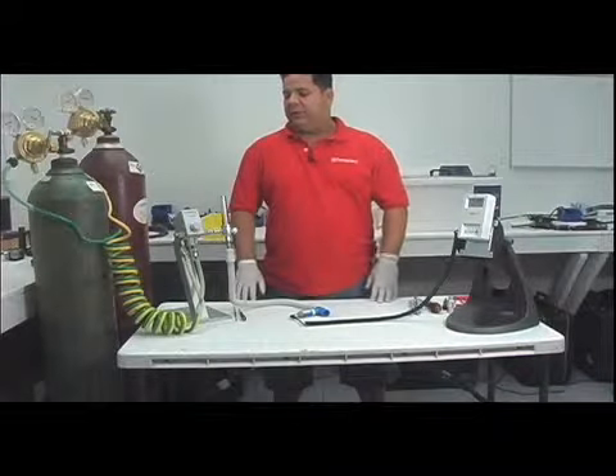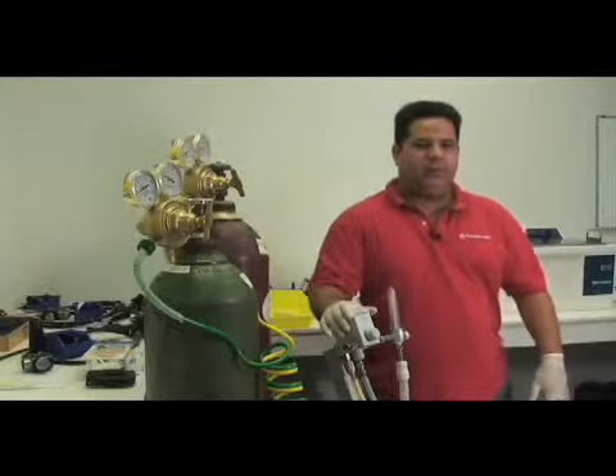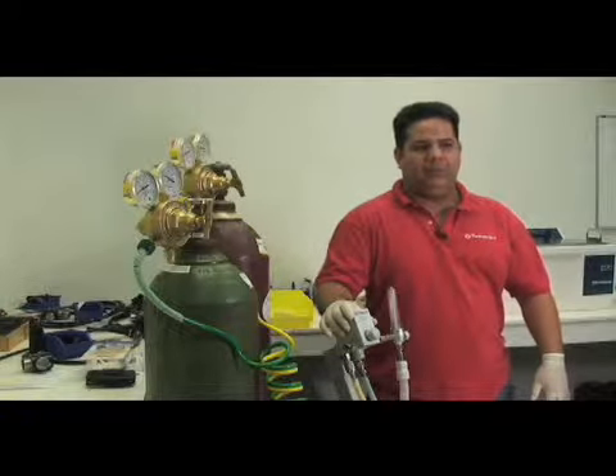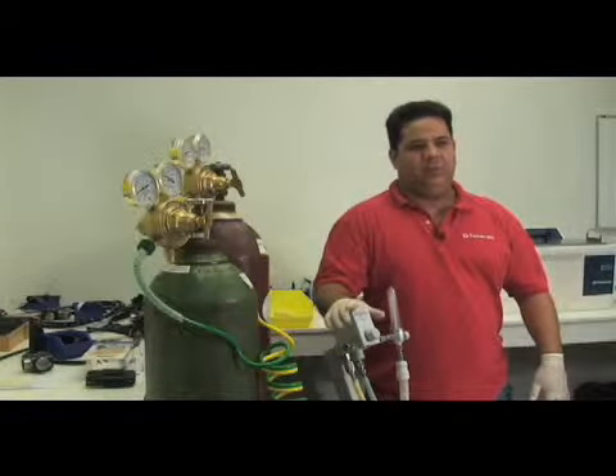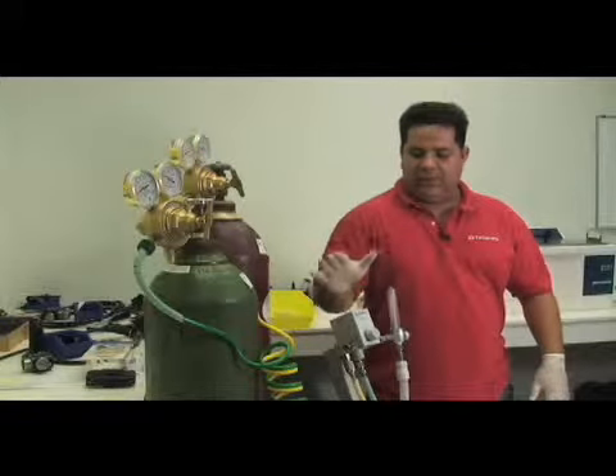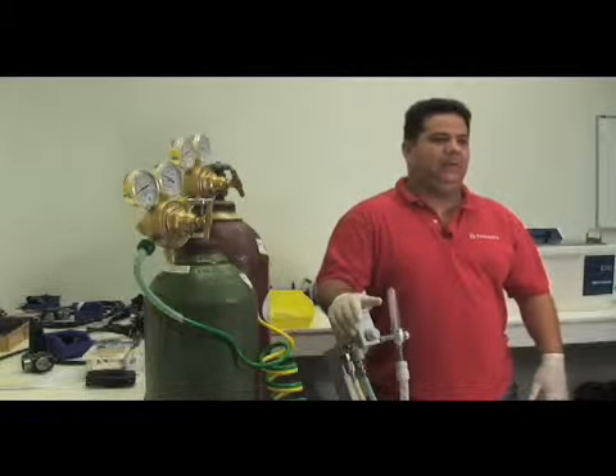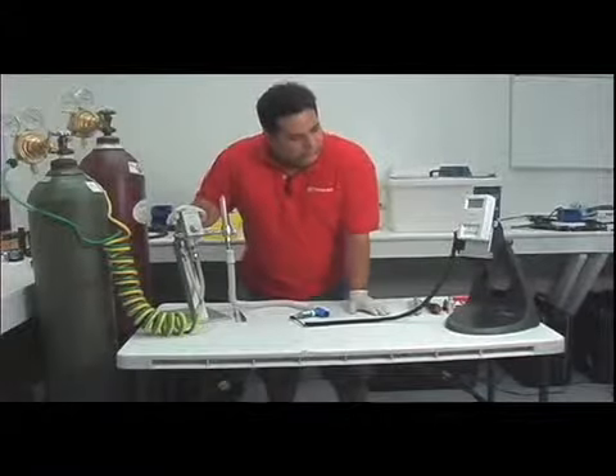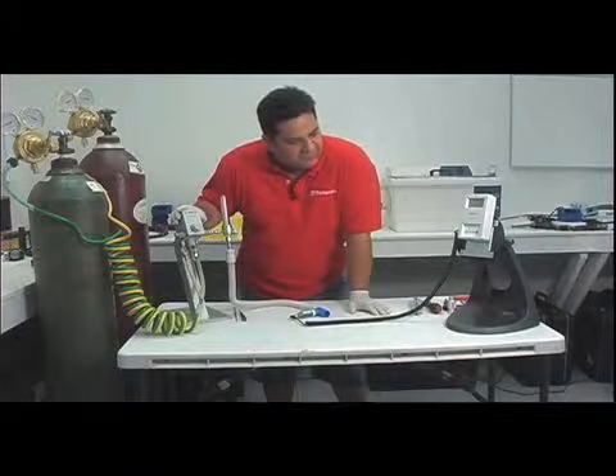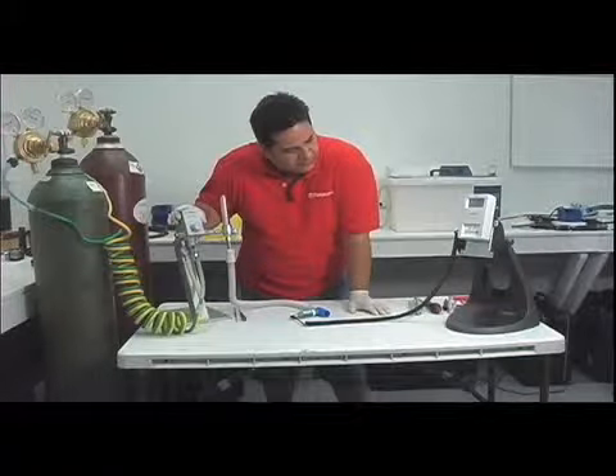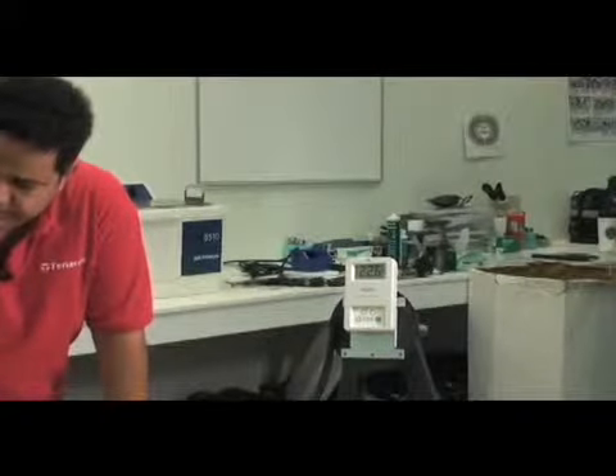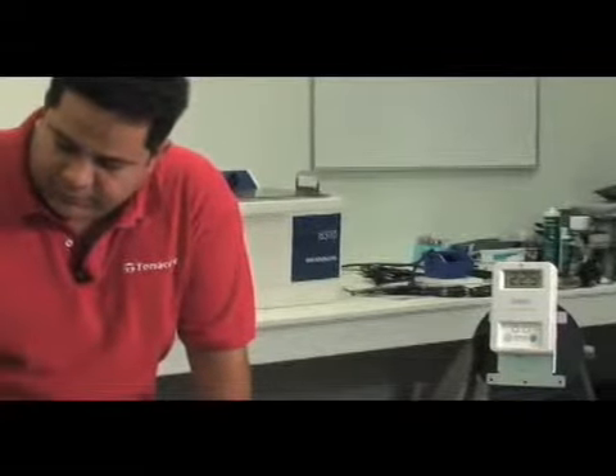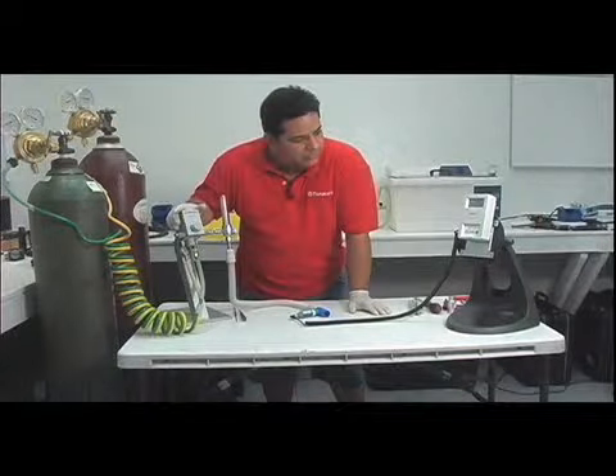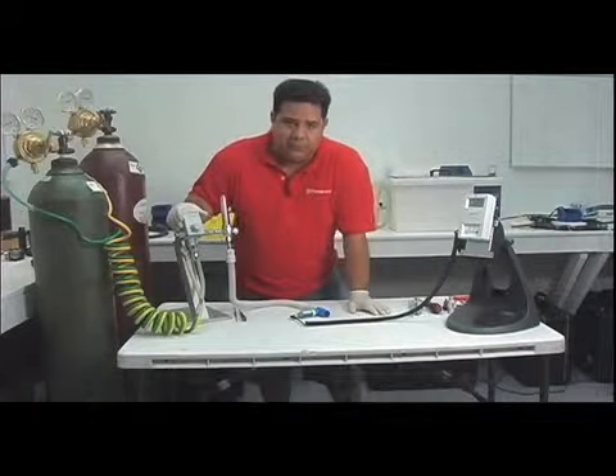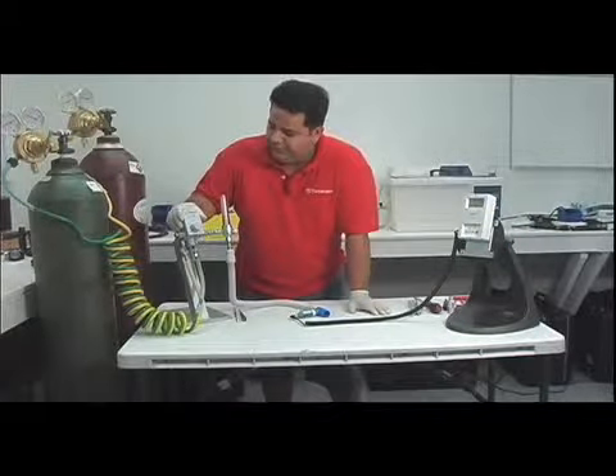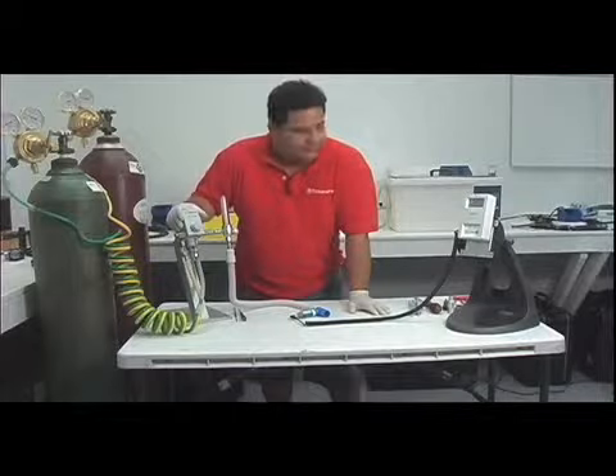Alright, since we now have all the readings calibrated, we're just going to double check and go back to every single one of them to make sure we're within specs. Once we wrap this up, then we can proceed to the alarm calibration. So we're reading our 21% concentration, and as you can notice, our oxygen analyzer is going to settle. Then we're going to read our 30, 60, 90, and 100, and that will do it. This is the necessary reference for you to have a good calibration on your blender.